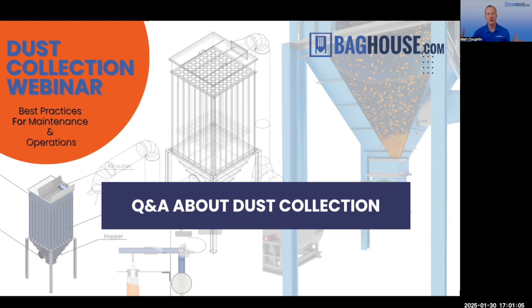So if you have a rotary airlock, for example, the idea is that you have a leak-free, airtight piece of equipment that provides an airtight divider between the hopper, which is at a certain pressure, and the atmosphere below the hopper, which is at regular standard atmospheric pressure. What can sometimes happen is your rotary airlock, which is a little rotor, has tips on it, sometimes made from different materials, but they're designed to have a really tight clearance to maintain that leak-free, airtight operation. So the dust falls through, but the air basically stays at its pressure.